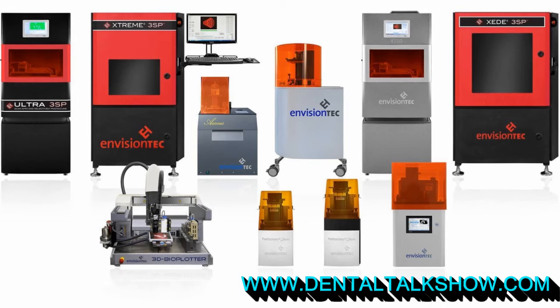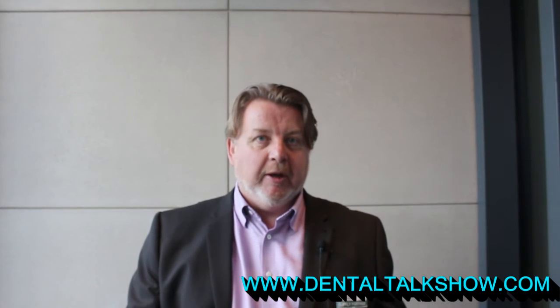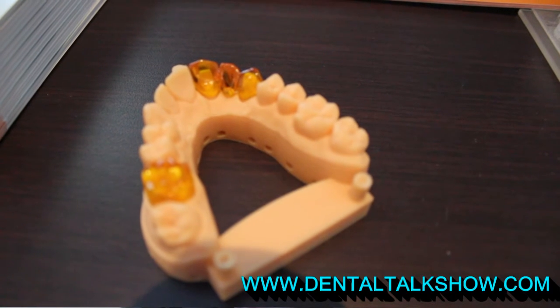Our smallest machine is designed for small volume production of copings and crowns and very intricate small parts, all the way through to our largest machine, called the XEDE. This uses the 3SP laser base system and has a build envelope of 457 by 457 millimeters, giving us typically around 100 models in a build, with a typical build taking somewhere in the region of three and a half hours.